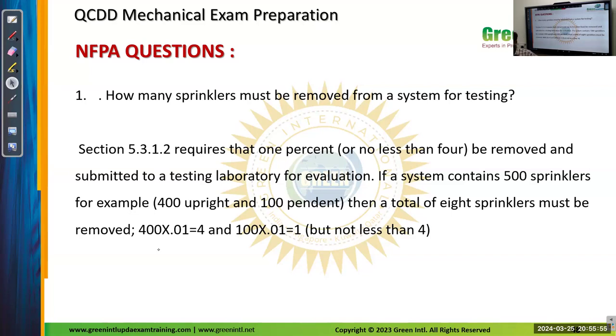No, actually. Here you mentioned 400 by 0.01 come 4. Yes. And the 100 by 0.01 come 1. Total now I remove for this 500 sprinkler 5 pieces. Yes, if it is 1%, there are 2 conditions. Okay, either 1% or 4 pieces. So there are 2 types of sprinklers, upright and pendant. If you are taking 1% from this, that is 4, and 1% from this, that is 1. Total 5 pieces. Your point is correct.